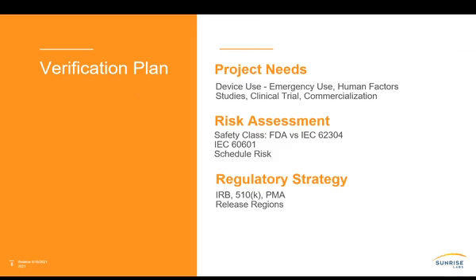And then from a regulatory strategy, this plays in pretty closely with safety class, but you may have different regions. So again, if you're going to Asia Pacific or the US or maybe Europe, if you're doing EMI testing, you're going to have to look at different voltage ranges. So if you're doing Japan and Europe, Japan is 100 volts. You have to look at 10% under that, so that's 90 volts, in terms of how the product performs in terms of performance and emissions immunity. And then on the Europe side, you're going from 240 to 256 or 260, I can't quite remember. It's 10% over.